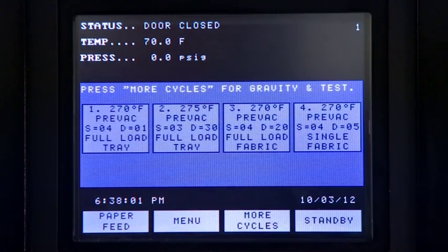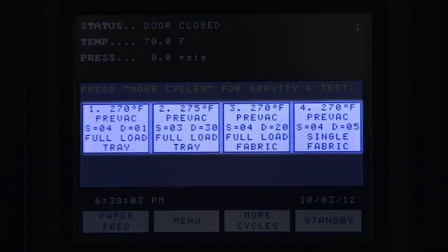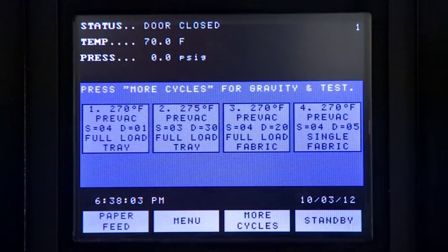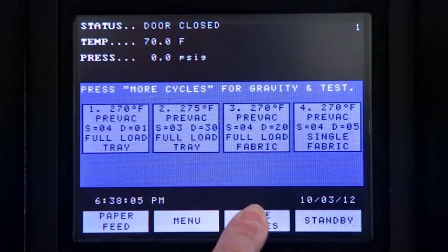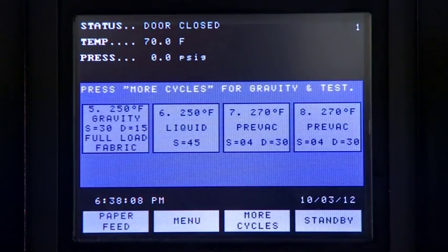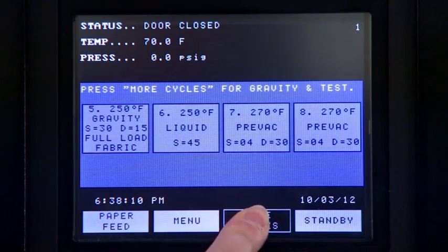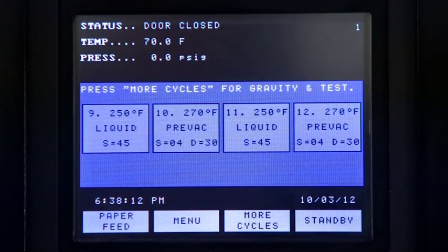4 cycle selection touchpads can be shown on the screen. Each pad displays the basic parameters of the cycle: the cycle name, sterilization exposure temperature, sterilization exposure time, and dry time. Additional cycle options may be selected by pressing more cycles. The AMSCO 400 series sterilizer can be programmed to retain values for up to 12 separate cycles.